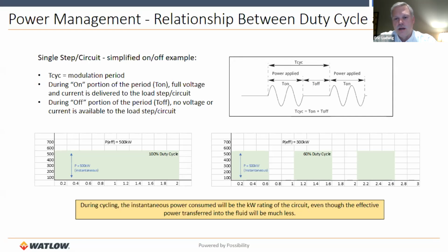On the right-hand side, you'll see that we start to cycle this. This is a 60% duty cycle graph. So it's on 60% of the time during that modulation period and off for 40% of the time. So for 0.6 seconds, this signal is on, and for 0.4 seconds, it is off. This has a modulation period of 1 second to make the math easy here. So while this is on, you can see that the instantaneous power that the system consumes is a full 500 kilowatts. But the effective power over that 1 second period of time is actually only 300 kilowatts.